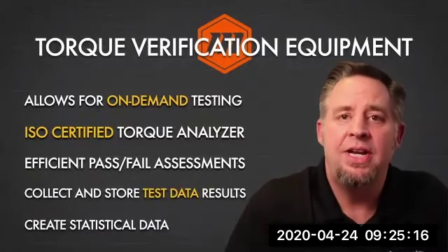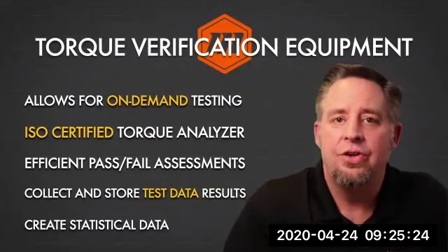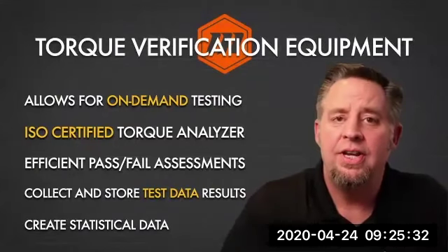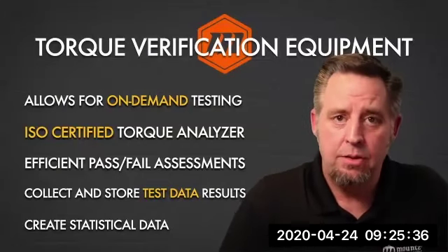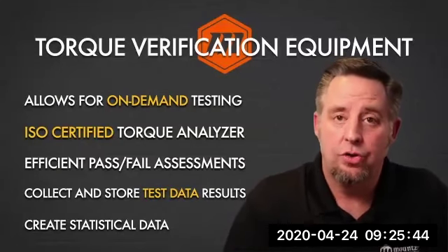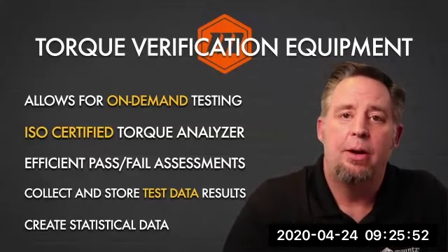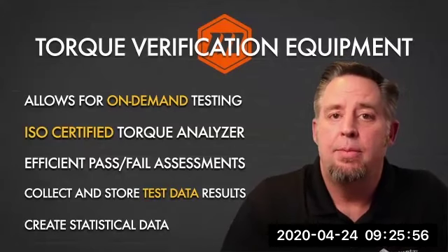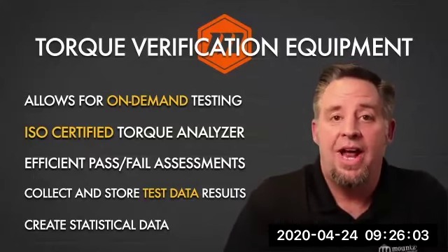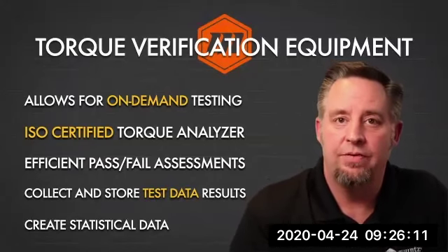The equipment that you would need to do a torque verification for on-demand testing would be a torque analyzer that is portable, that you could use, that would have a battery with it. It could either be a handheld unit, or it could be an analyzer that could be mounted to a cart or a bench for specific higher torque readings that may need to be taken. Obviously, it would need to be ISO certified. It should have the ability to issue a pass-fail assessment, and also be able to collect data, store that data, and provide you with any statistical analysis as well. That's the equipment that you would need to do the torque verification.